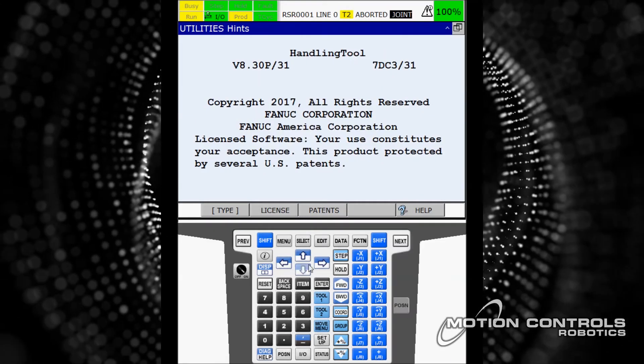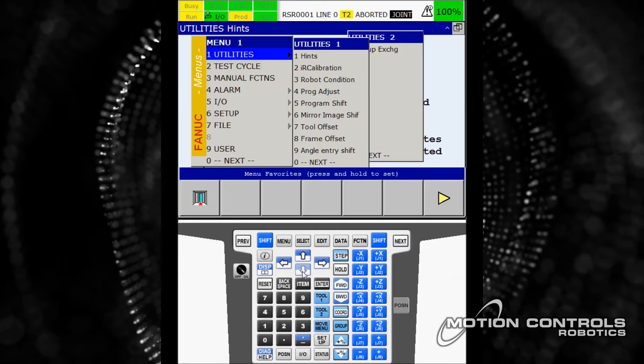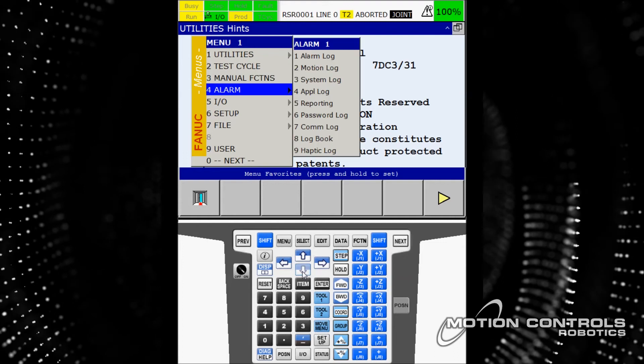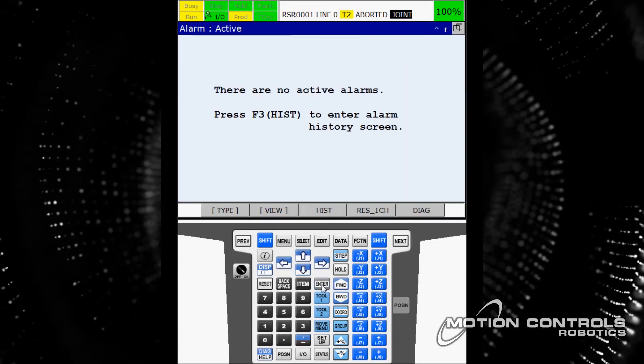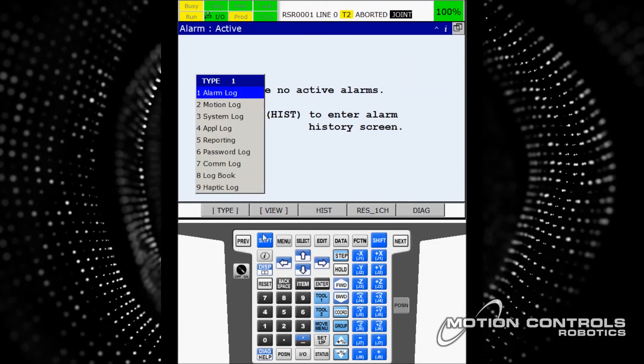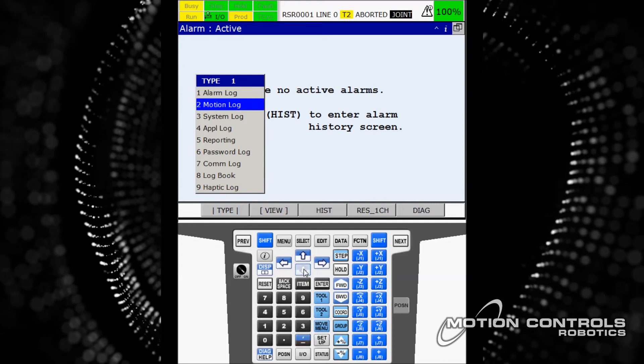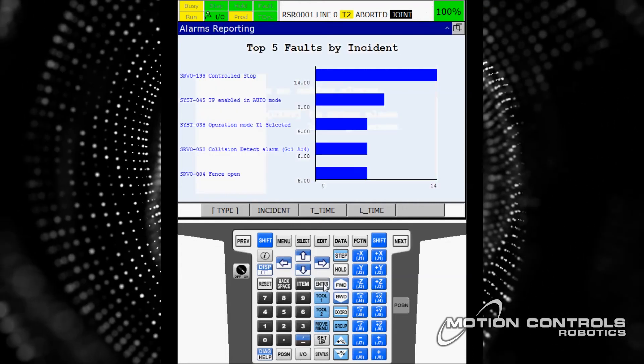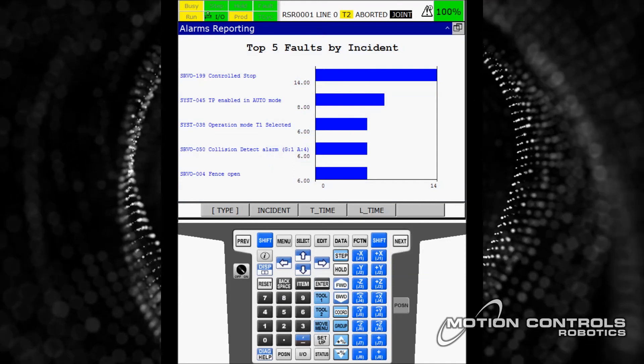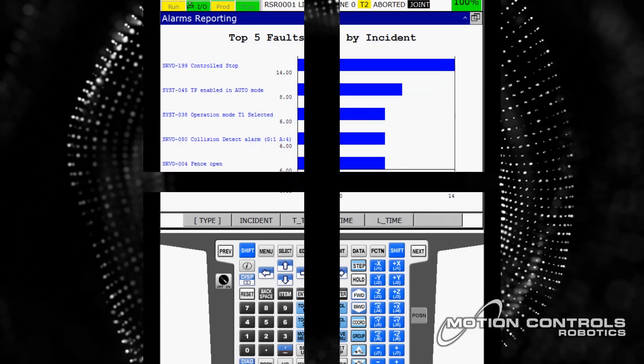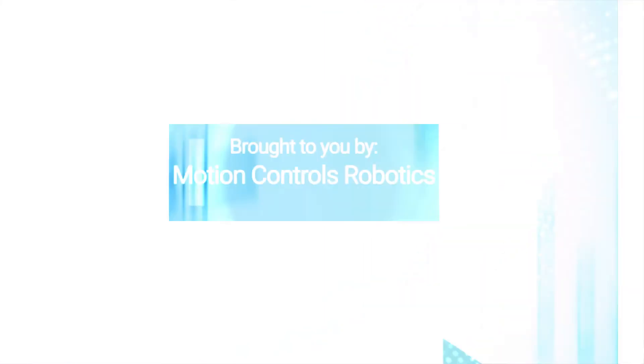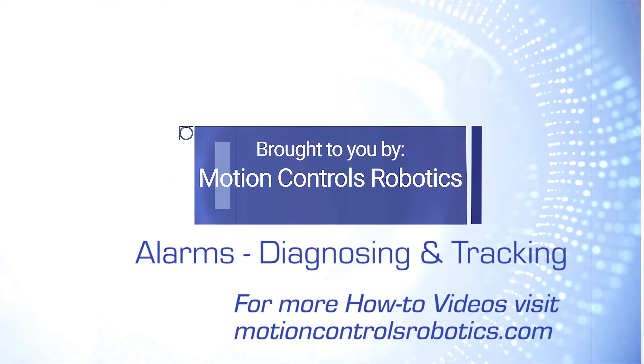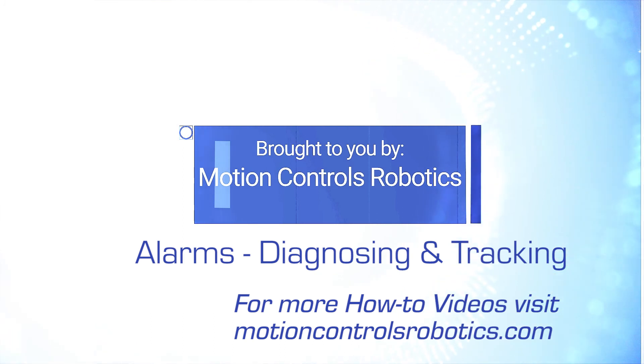To view a reporting graph, select Menu, arrowing down to Alarms. This brings up the Active Alarm screen. Once on this screen, select the Type option on the top-line menu, arrow down to Reporting and hit Enter. The reporting screen shows the top five faults by incident.